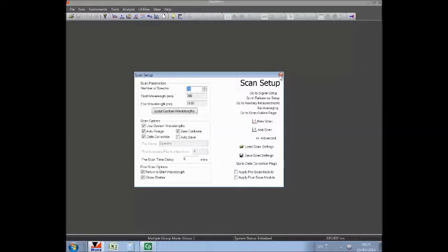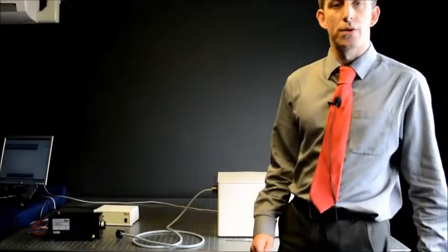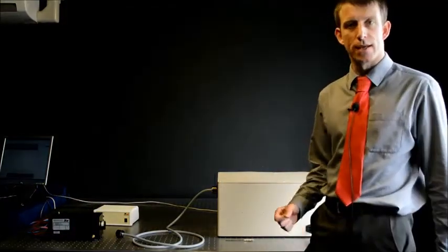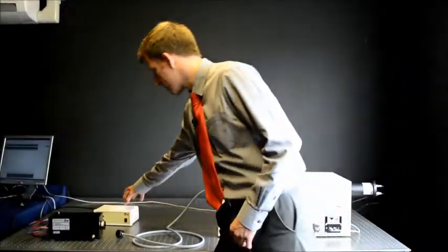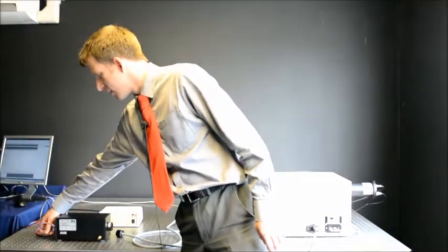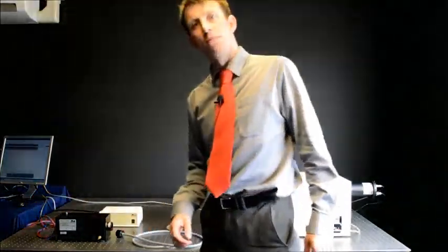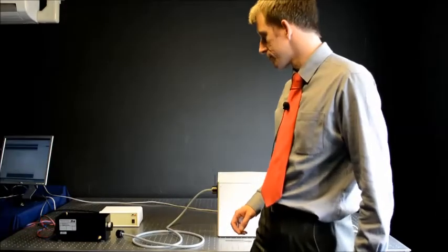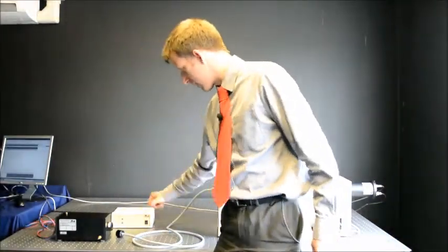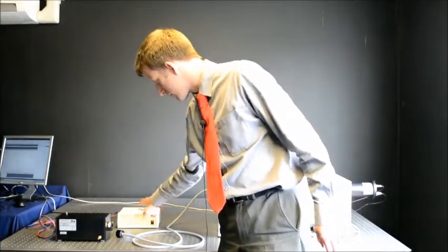Where a calibration in the UV is required, we should also look to calibrate the system with the CL7 deuterium lamp, which we will look at now before measuring any sources under test. Where measurements are required of spectral irradiance below 300 nanometers, then we must calibrate the system with the CL7 deuterium lamp. The CL7 deuterium lamp has its own dedicated 706 power supply, which is connected to the source via the red, black and blue cables, and we can simply, with the mains connection in place, power the 706 on.